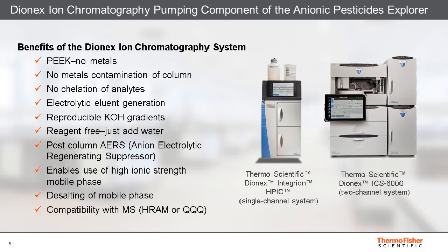Additional advantages of the Dionex ion chromatography system include the inertness achieved using PEEK and no metals along all analyte pathways. The metal-free IC system eliminates issues of polar analyte adsorption by metal ions leaching from the LC system. Reagent-free electrolytic eluent generation removes tedious mobile phase preparation, and gradients generated in situ using the eluent generator cartridge are extremely reproducible, resulting in very stable retention times.